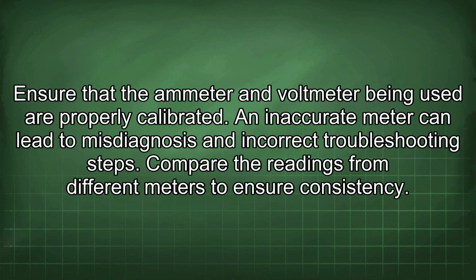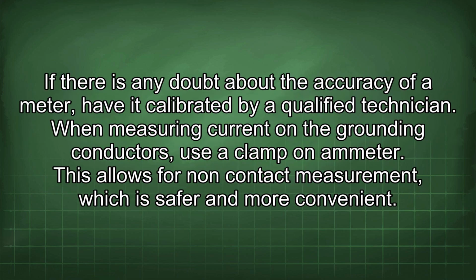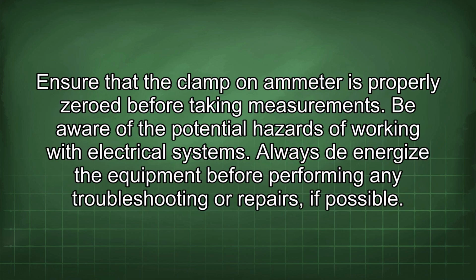Ensure that the ammeter and voltmeter being used are properly calibrated. An inaccurate meter can lead to misdiagnosis and incorrect troubleshooting steps. Compare the readings from different meters to ensure consistency. If there is any doubt about the accuracy of a meter, have it calibrated by a qualified technician. When measuring current on the grounding conductors, use a clamp-on ammeter. This allows for non-contact measurement, which is safer and more convenient. Ensure that the clamp-on ammeter is properly zeroed before taking measurements.